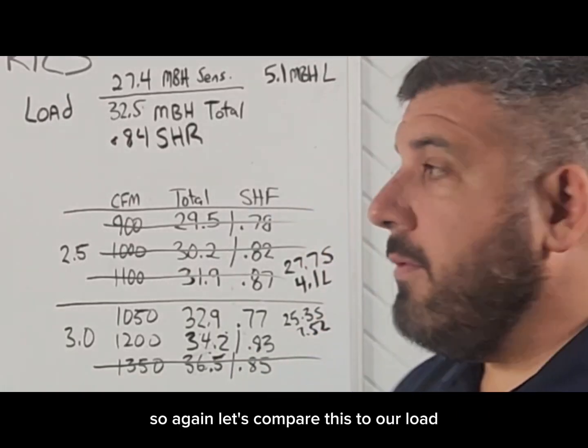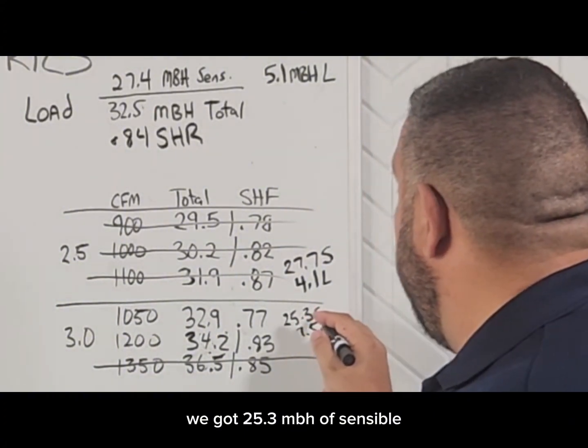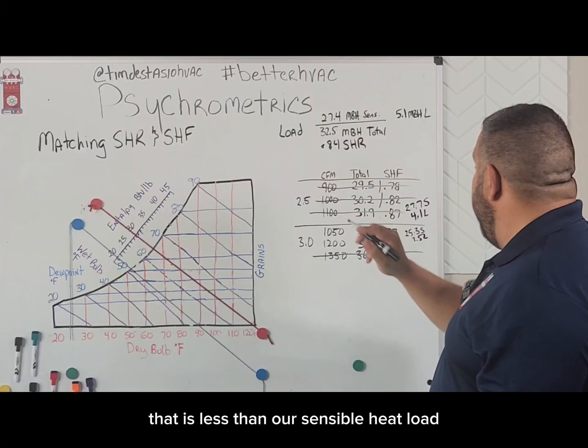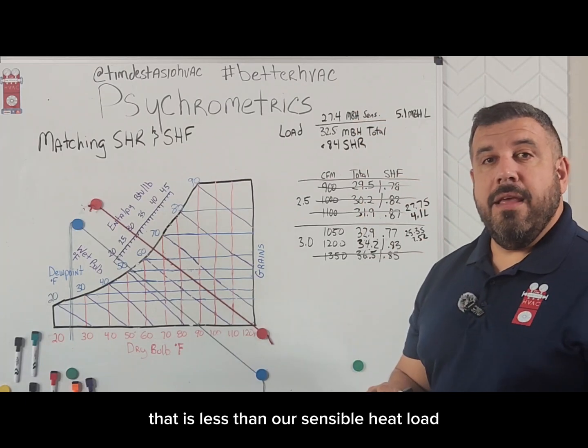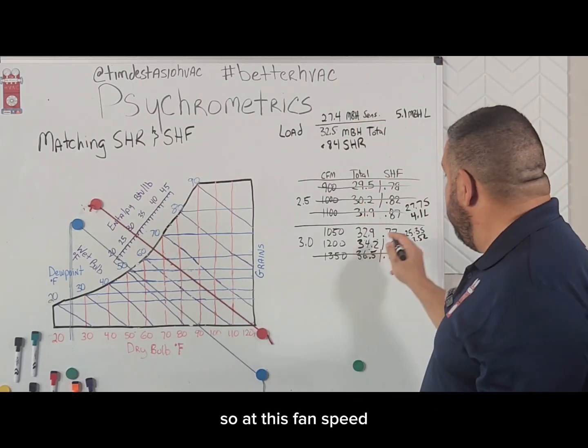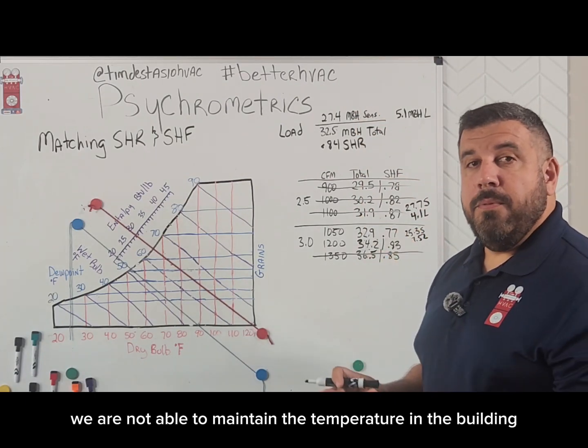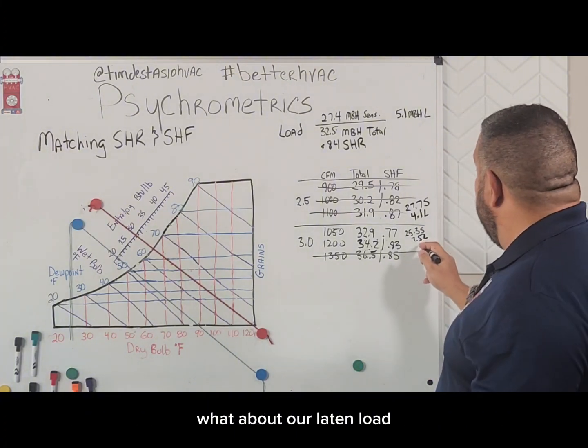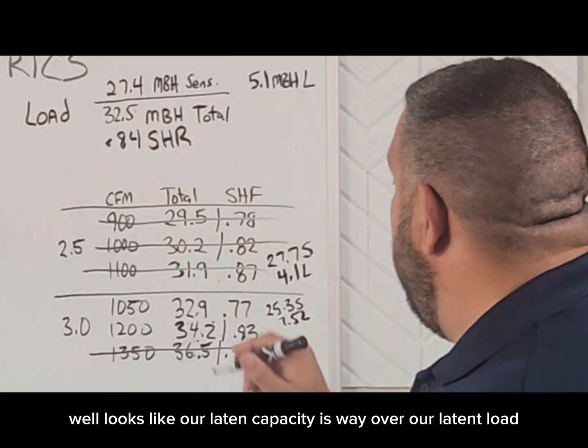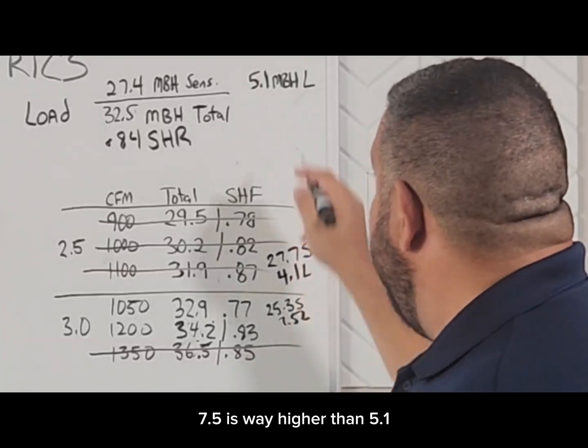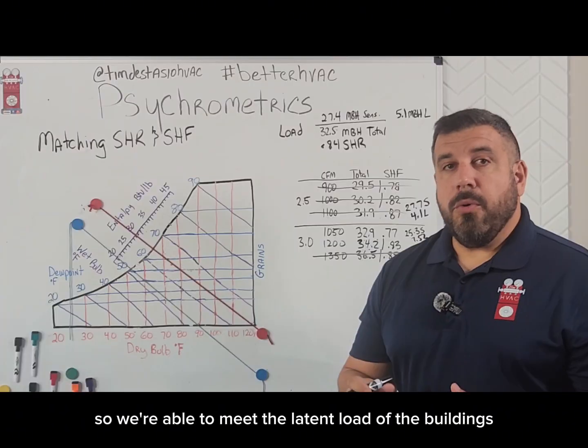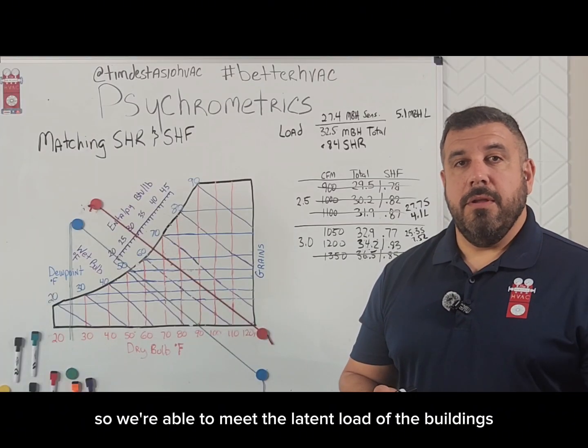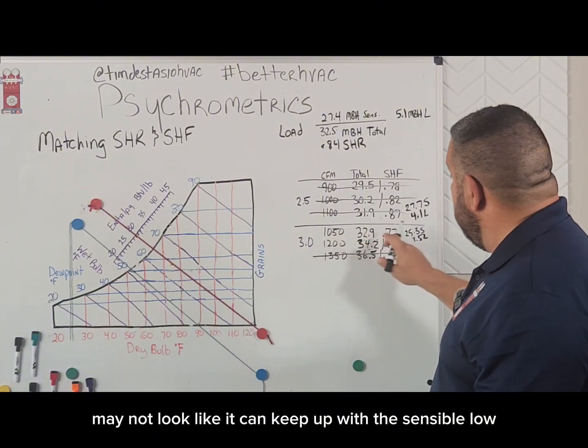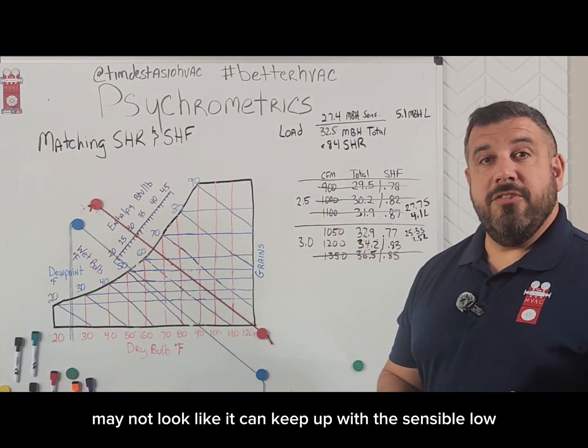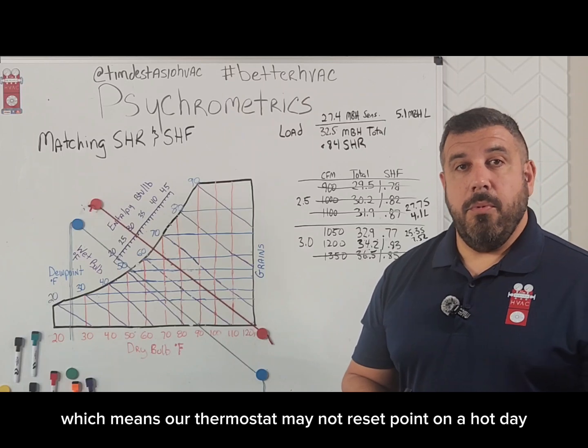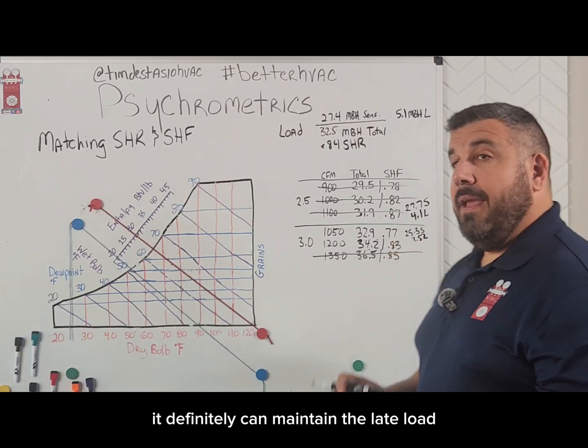So again, let's compare this to our load. We got 25.3 MBH of sensible. That is less than our sensible heat load, so at this fan speed, we are not able to maintain the temperature in the building. What about our latent load? It looks like our latent capacity is way over our latent load. 7.5 is way higher than 5.1, so we're able to meet the latent load of the building. So while the system on paper may not look like it can keep up with the sensible load, which means our thermostat may not reach set point on a hot day, it definitely can maintain the latent load.